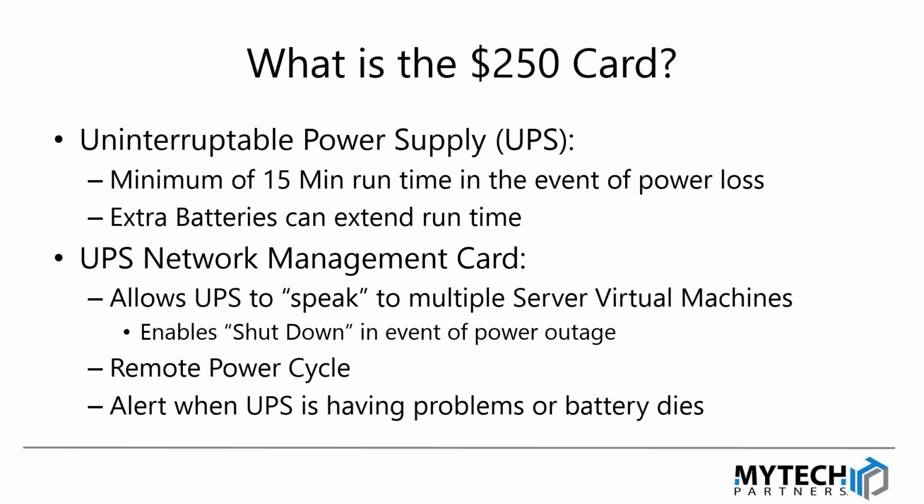Finally, getting to the UPS network card, why is this important? In the world of virtualization, in the last 7, 8, 10 years, as more small businesses use it, there's no longer one physical server to one server operating system ratio. There's usually multiple server operating systems to one physical server. The network card allows the UPS to actually talk to multiple servers, and you could have several different servers, and the network card can talk to all of them and be able to initiate the shutdown. So that's one of the ways in which they can speak to the current ways in which servers are deployed today, which is using virtualization.